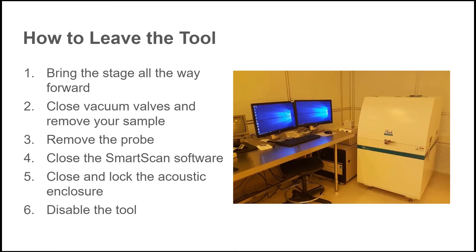After finishing your measurements, be sure to bring the stage all the way forward. Close vacuum valves and remove your sample. Remove your probe. Close the software. Close and lock the acoustic enclosure. And of course, disable the tool.